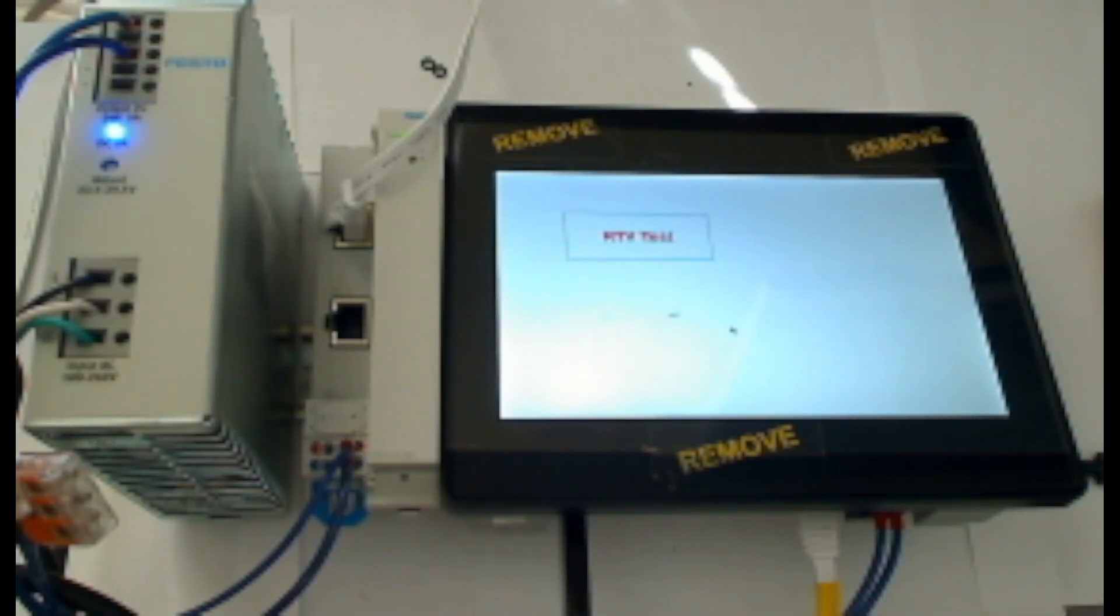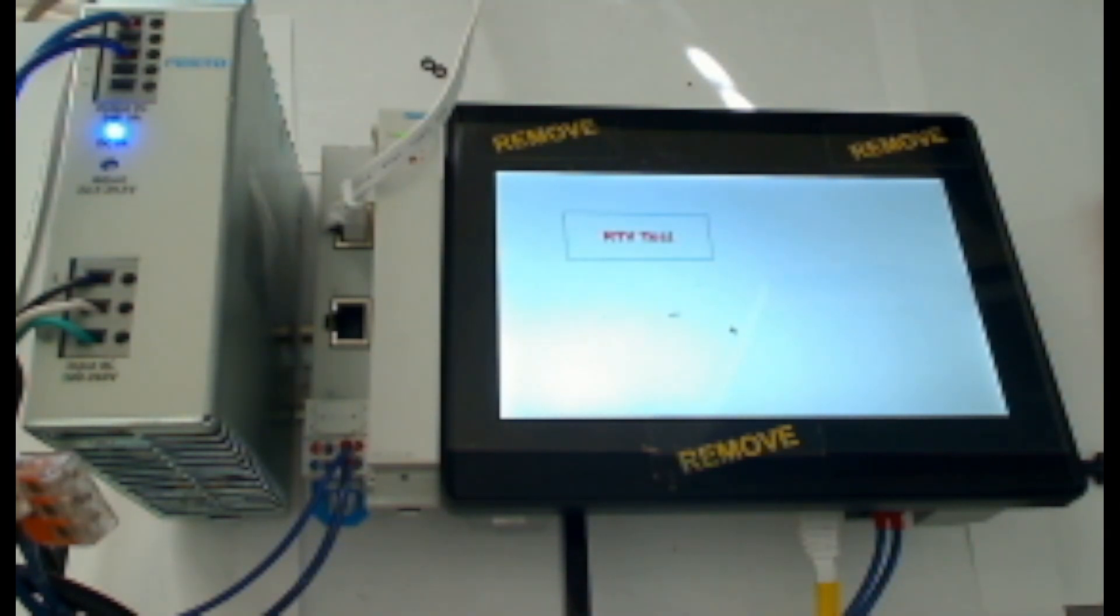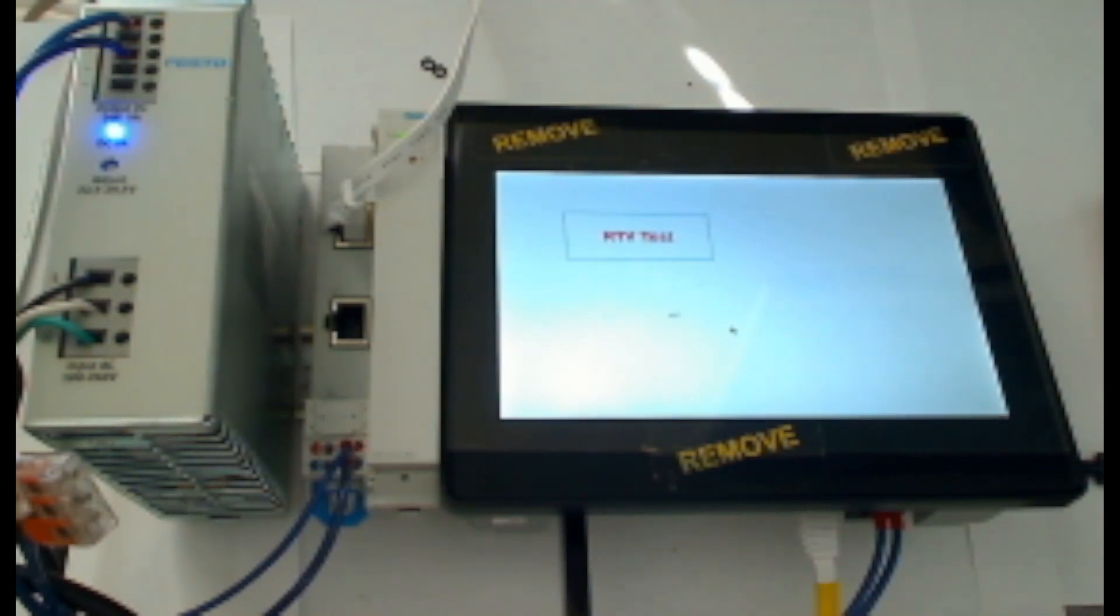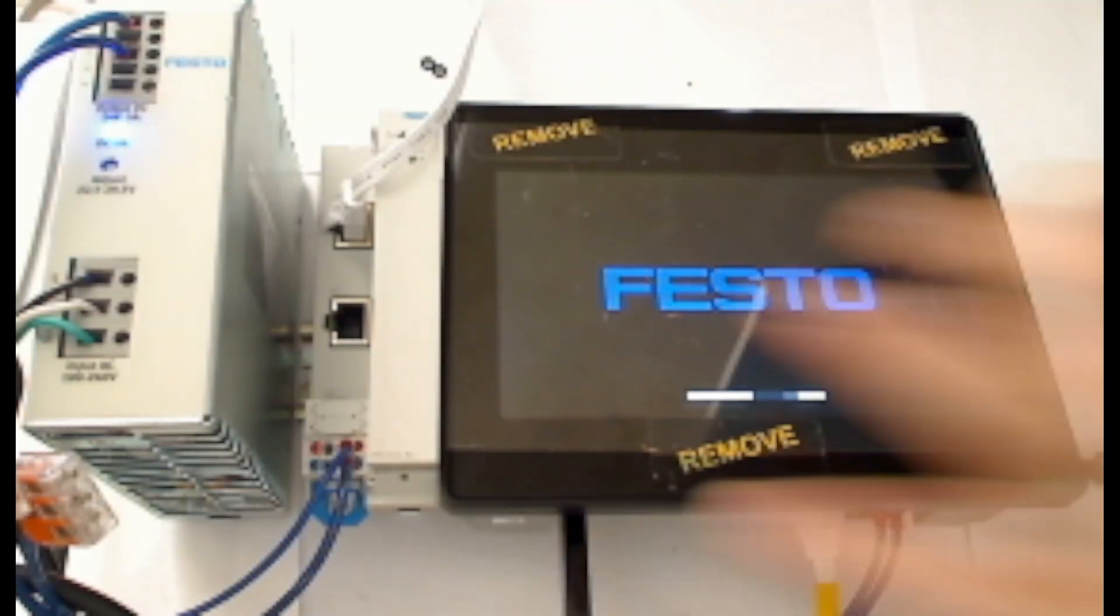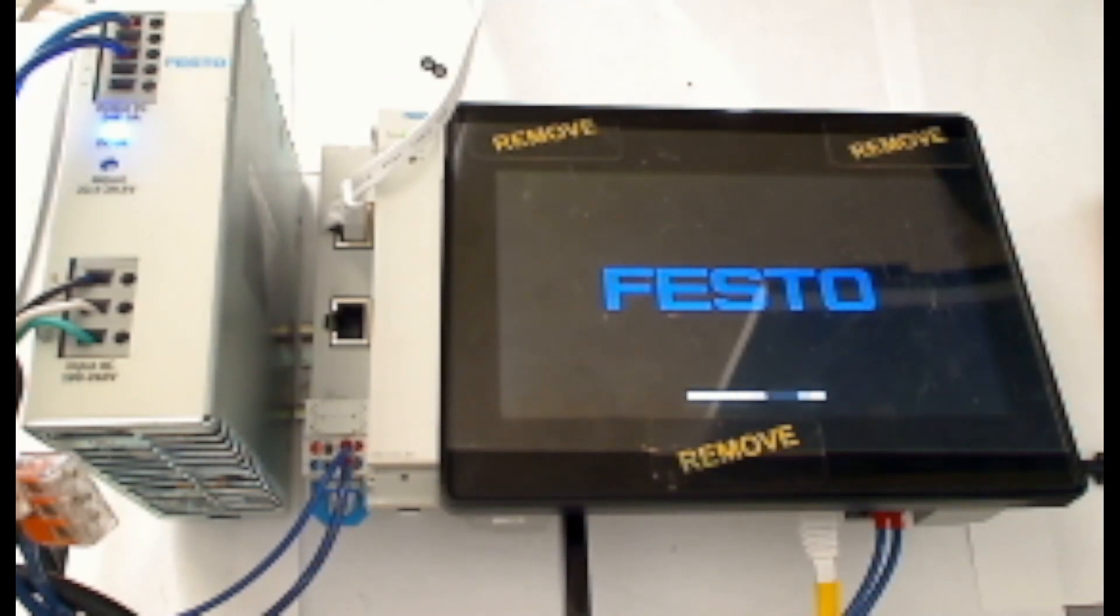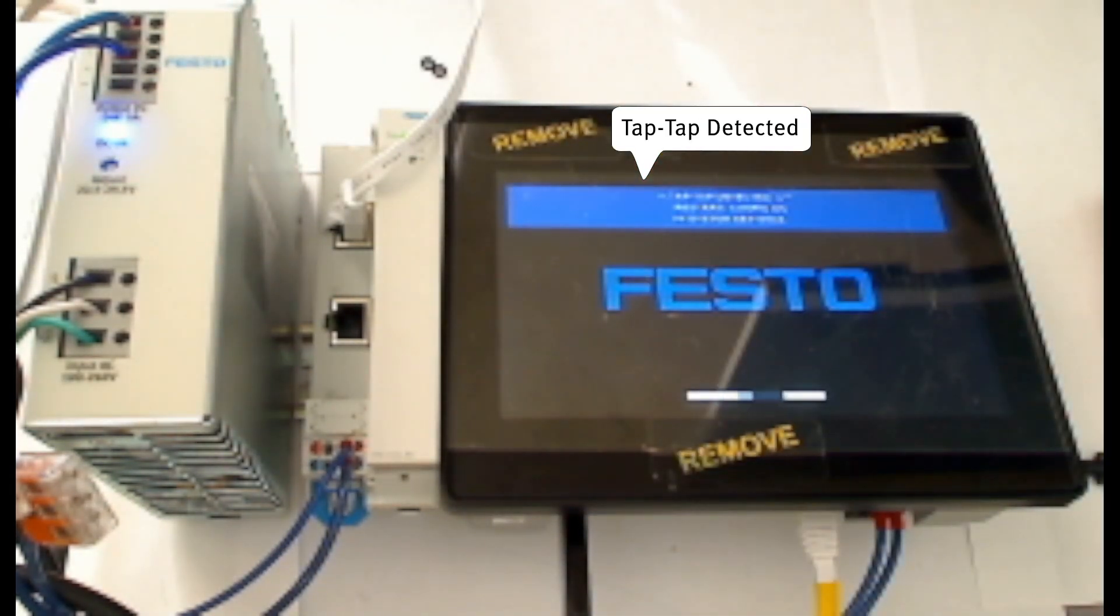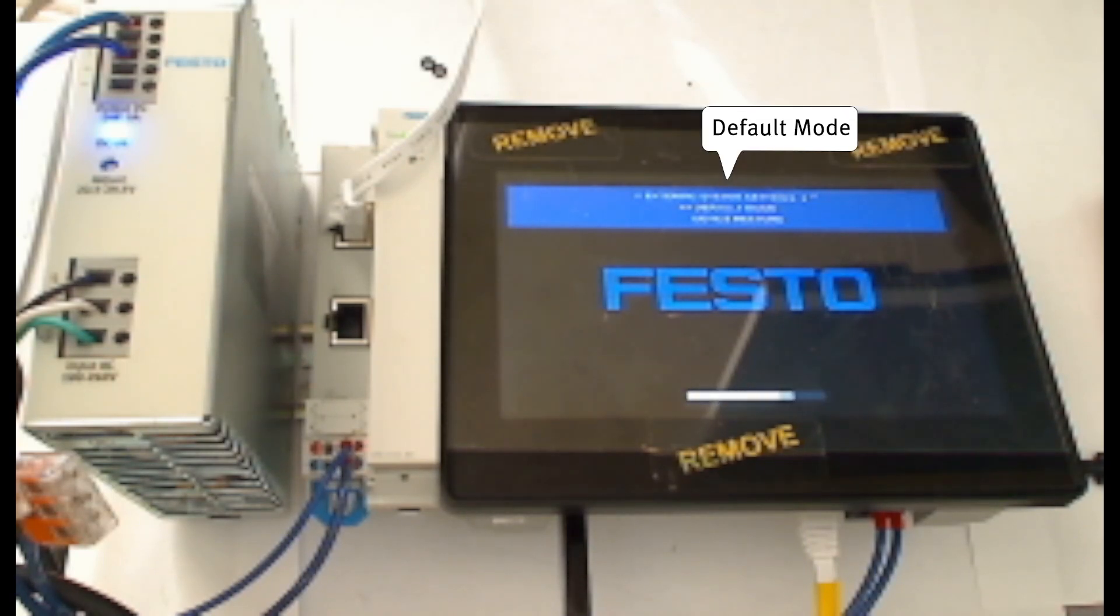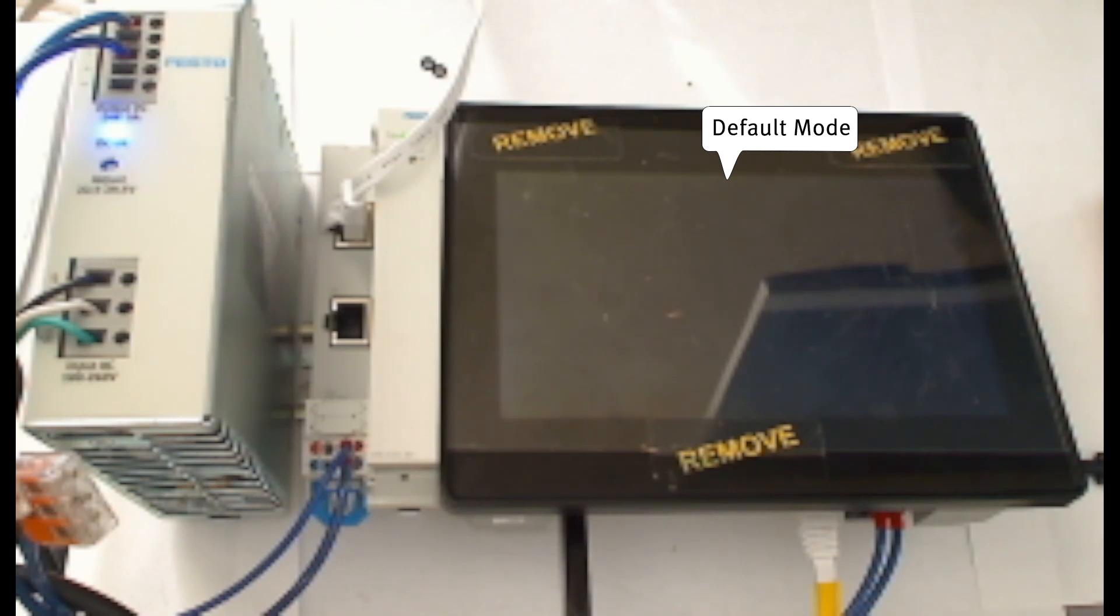One final thing that needs to be completed is to verify that the HMI will auto start in remote target visualization mode. To do this, I will power cycle the HMI. As the HMI is starting up, I'll double tap the screen. You may have to do this twice. You'll see it says tap tap detected and ask if you want to go into standard or settings mode. Entering system settings, I'll select default mode.